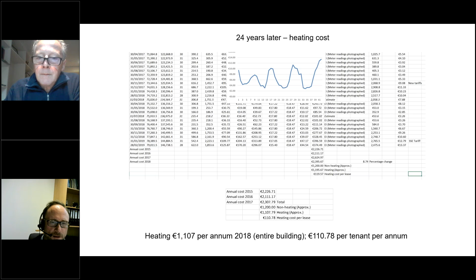Are there any calcium scaling processes in the borehole over time? Initially, we had a routine of backwashing the main plate heat exchanger, and we did that approximately once every year, and often a couple of times during the initial year, and we found no significant effect. So we haven't washed that in the last 15 years.